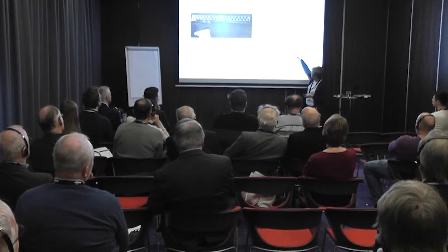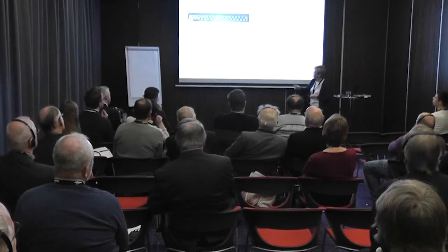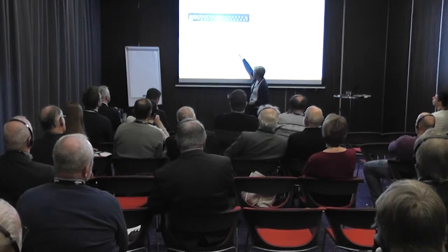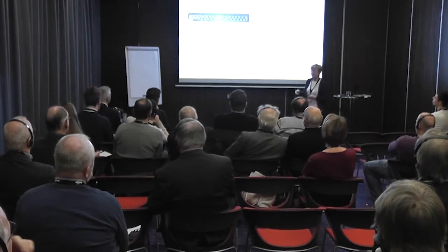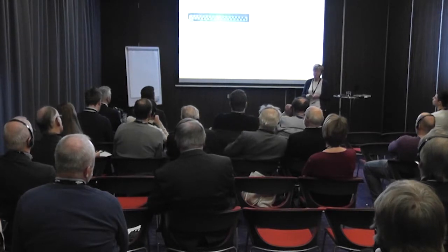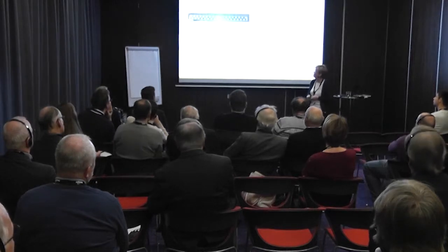distance. Here is the supply, and this is 34 centimeters, 47 and so on until 84, and at different heights. So there we measured what you see here. We measured the velocity, the standard deviation of the velocity, the turbulence intensity, and the draught rate. We had, I think, 3 or 4 different solutions, and ended up with one that was good for the reduced area. So that was a very happy ending of a very stressful situation.